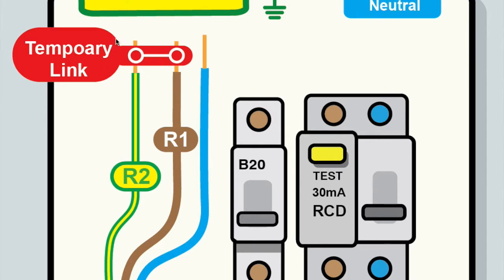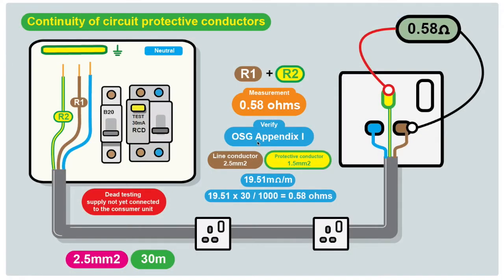Always remember to remove any temporary links as soon as you finish doing any testing. We've finished our test on the continuity of circuit protective conductors for this circuit. We've got a reading of 0.58 ohms which we've recorded, and we've also removed our temporary link.